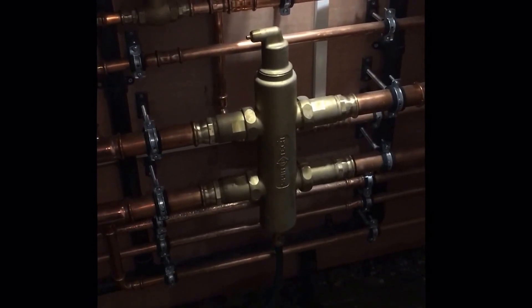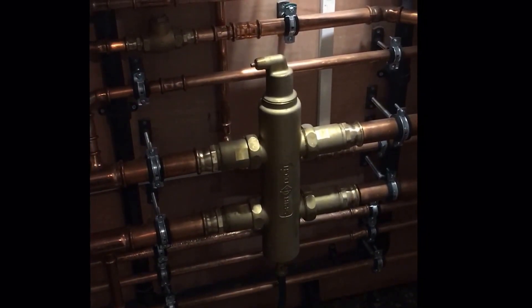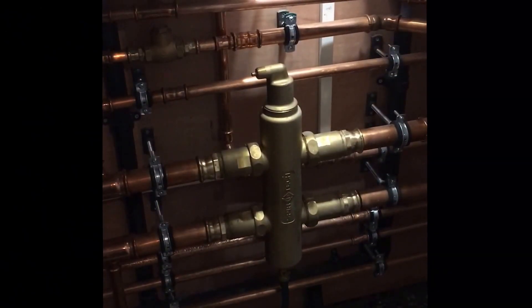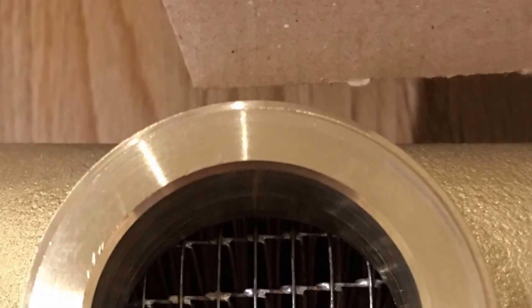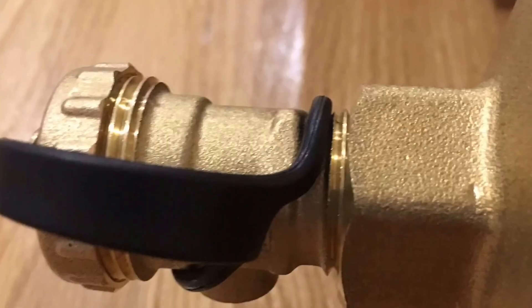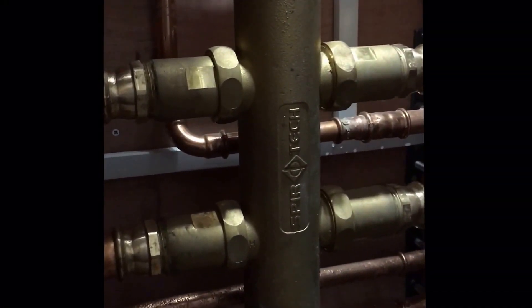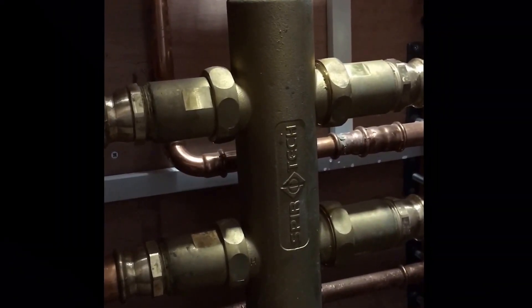So here we've got a Spirotech SpiroCross low-loss header. It's got the deaerator built in, it's also got the gauze inside which helps with dirt separation. It's got a drain off on the bottom, and that allows you to obviously drain the system — but not only that, when you do get some muck in the dirt separation, it all drops to the bottom and you're able to clean it out.